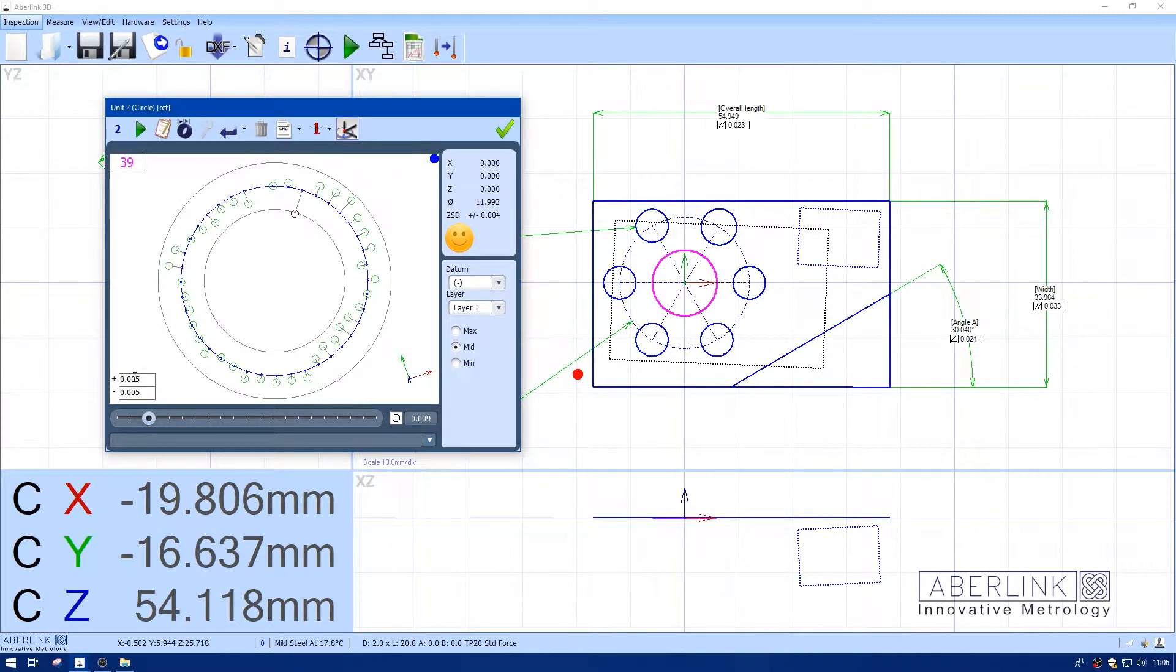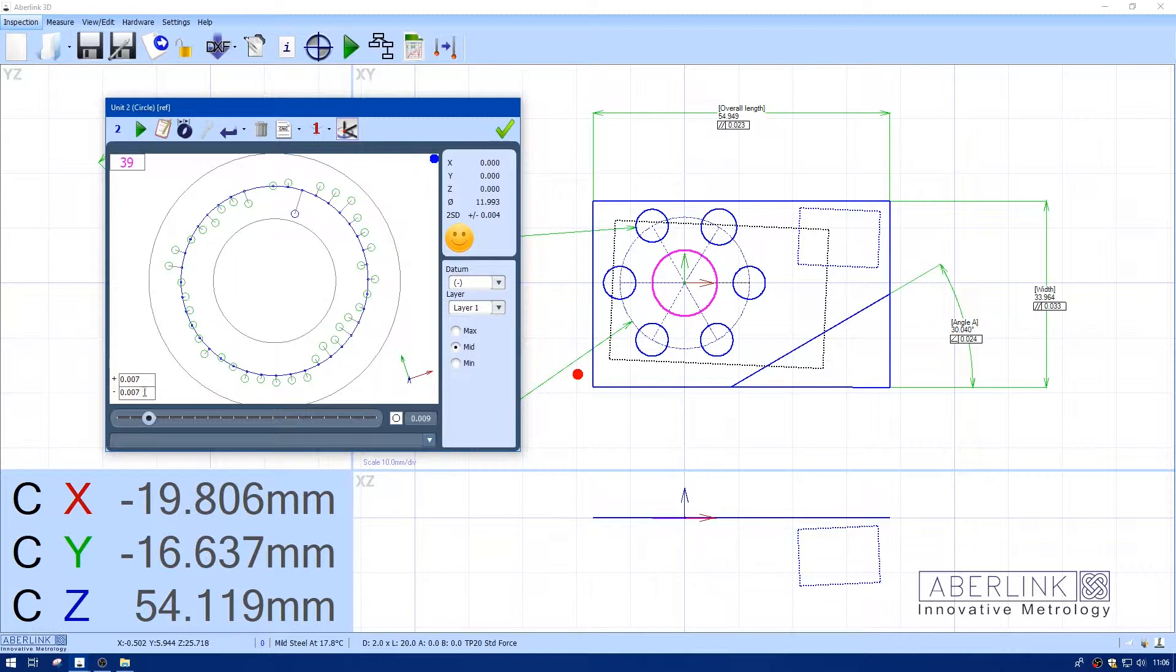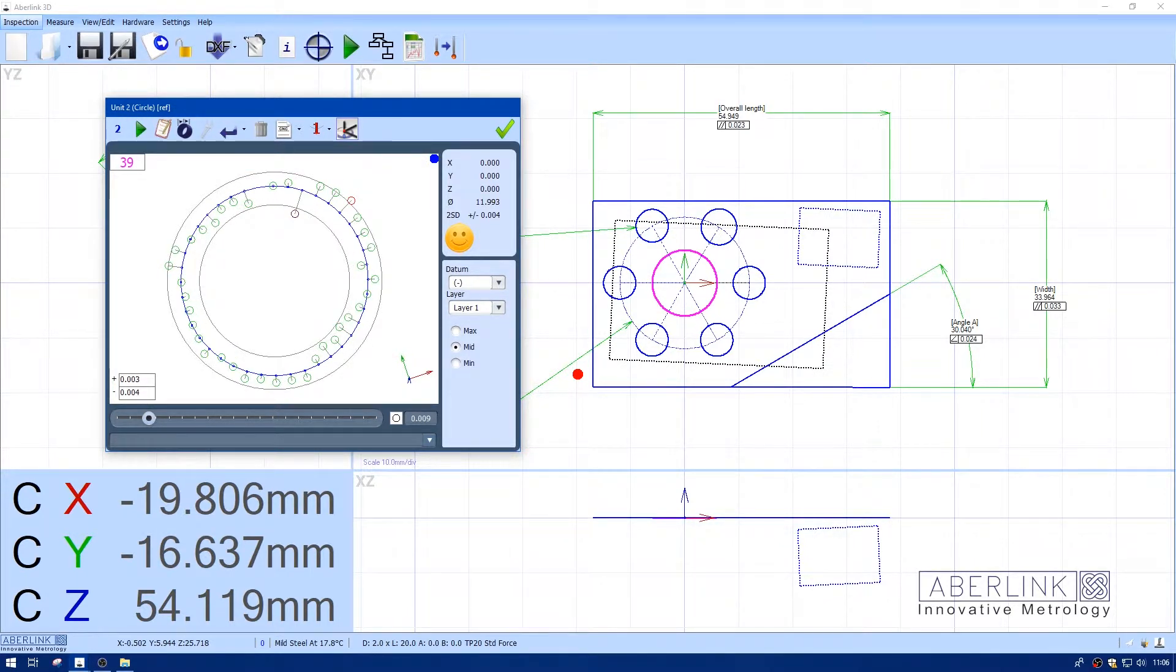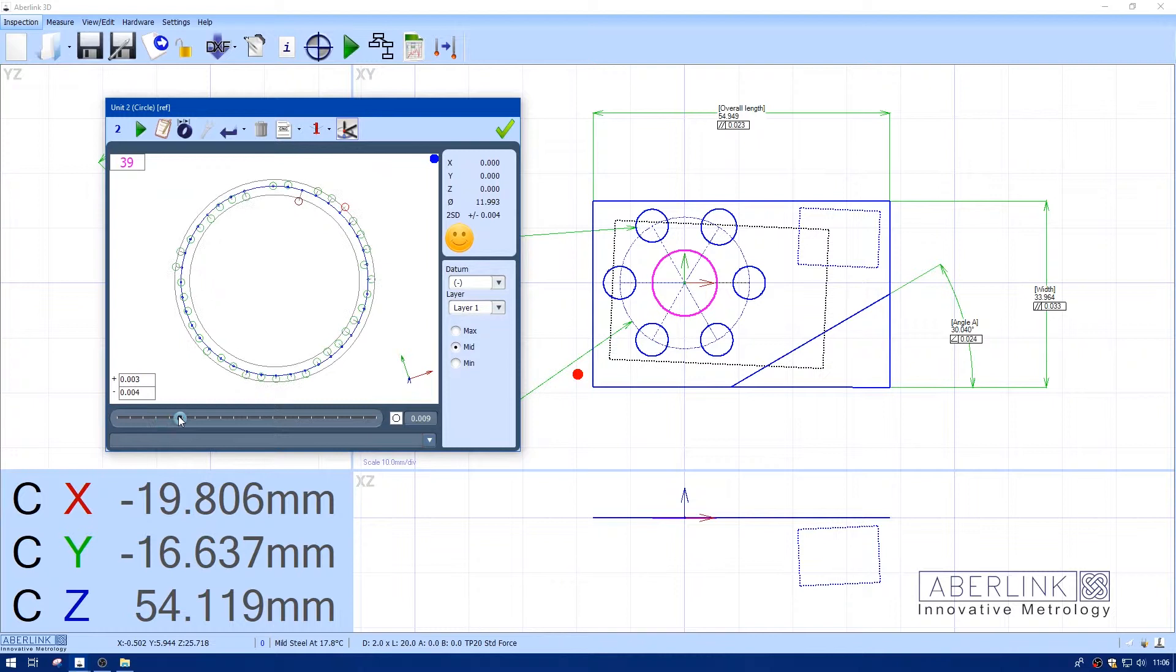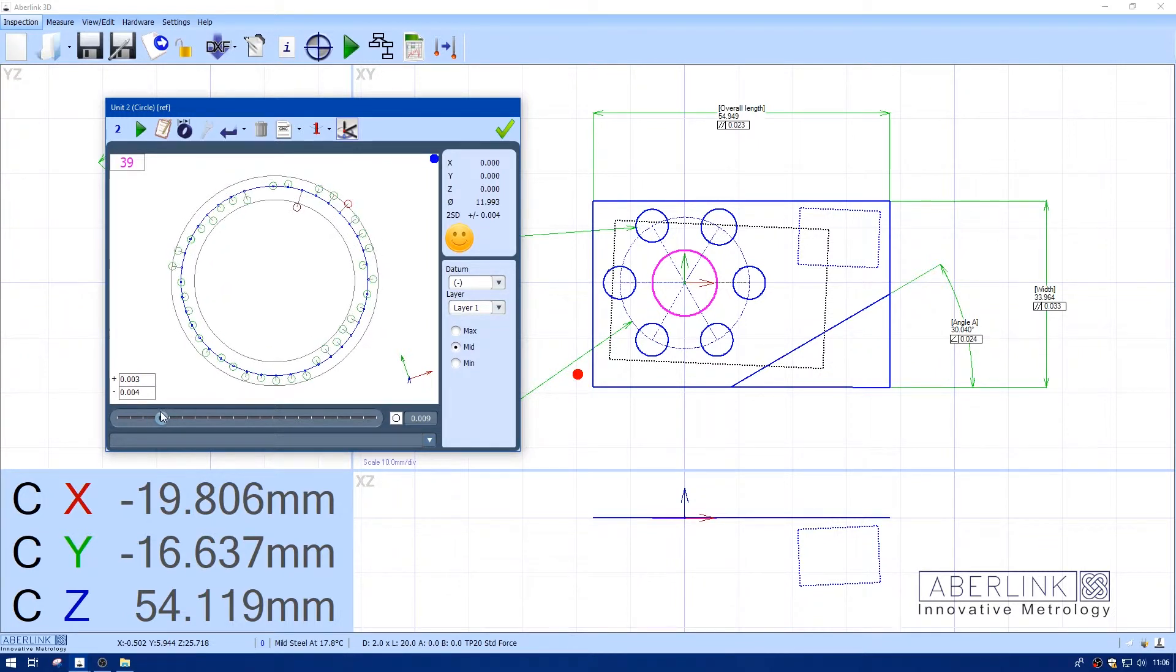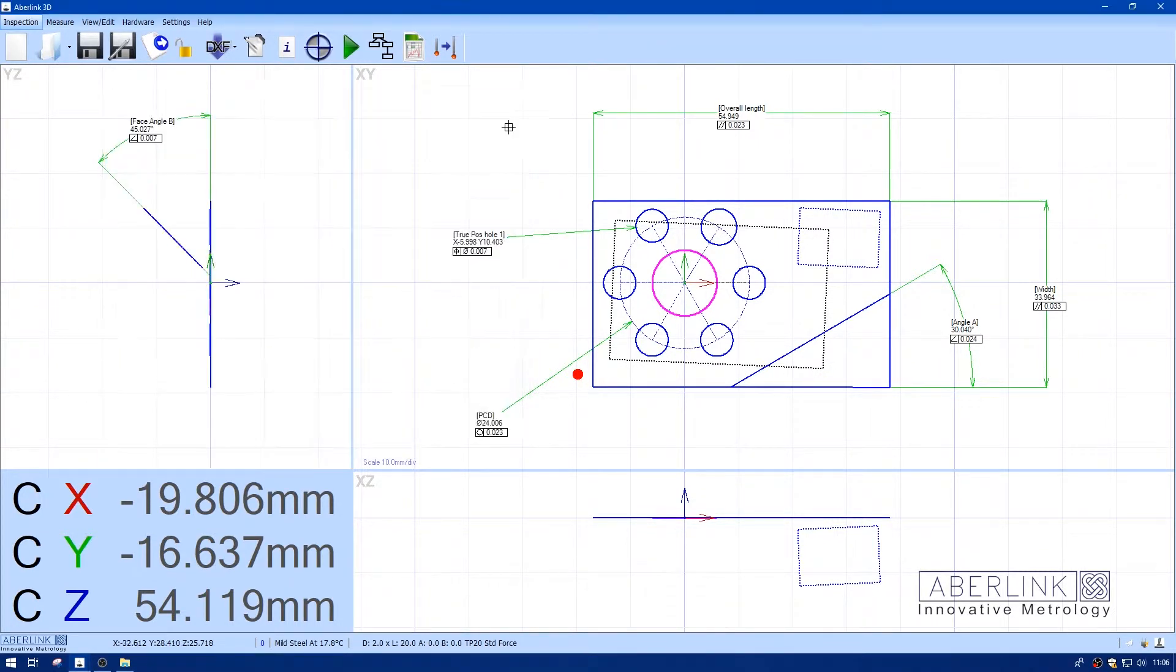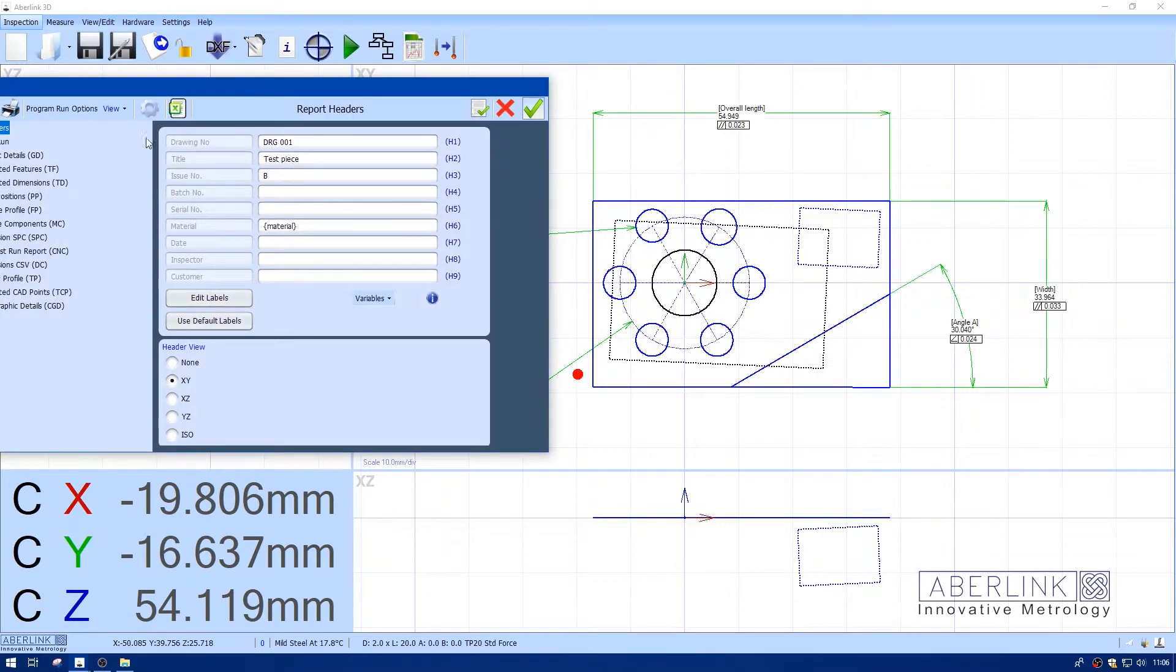So if you right click on it, you can see you've taken 39 points and you can see some form error. At the moment the plus or minus 5 micron bands are showing. I can change those to whatever I like. The top one and the bottom will also change, so I can change the bottom one independently. I can adjust the zoom to suit my report.